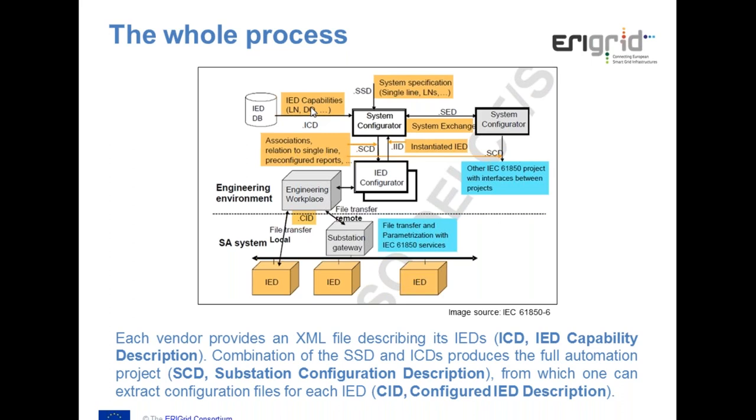And then one last question from Mr. Resch. What are the typical data exchange via SCADA over the CIM interface? The CIM SCADA interface by itself just transfers measurements and controls, so it's a very direct interface to the SCADA. The main point is what kind of higher level CIM services you use, and in ERIGrid, for example, I have shown the idea to use a state estimator function, like a demonstration of this kind of CIM interface.